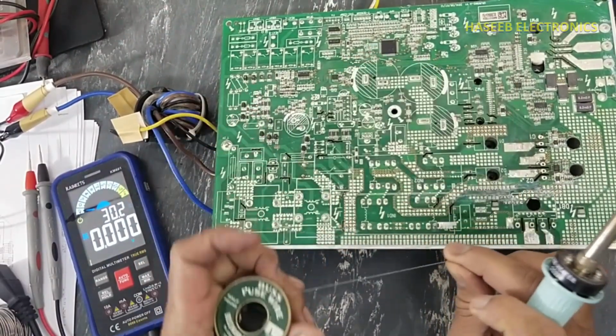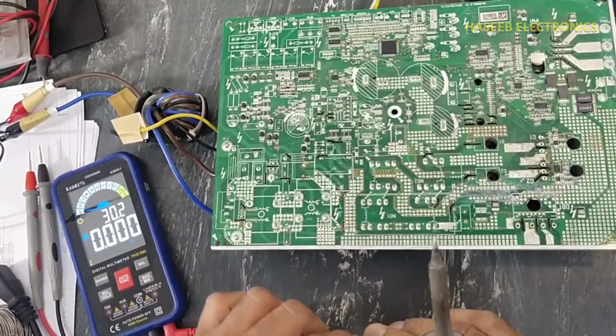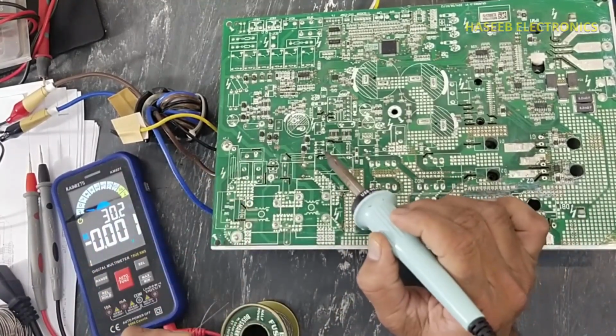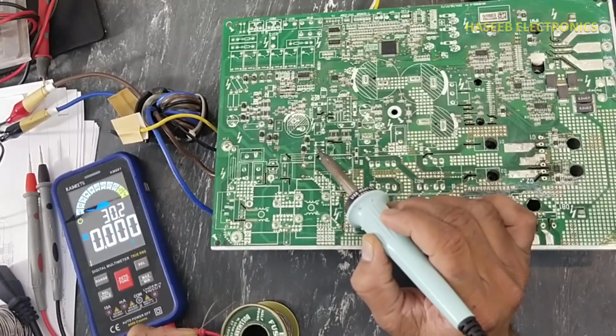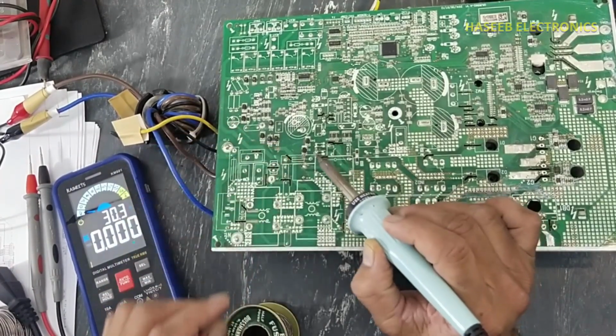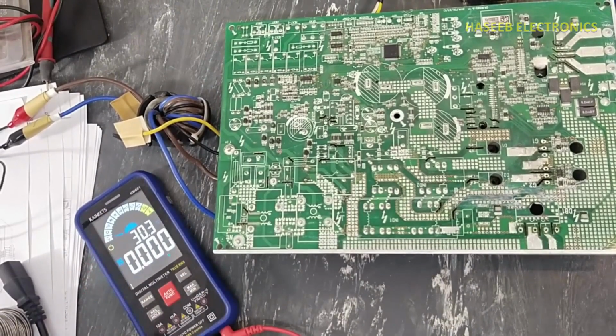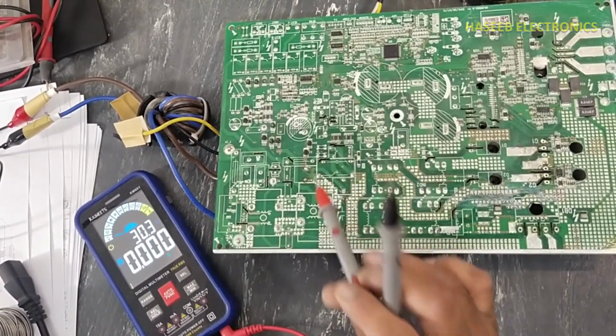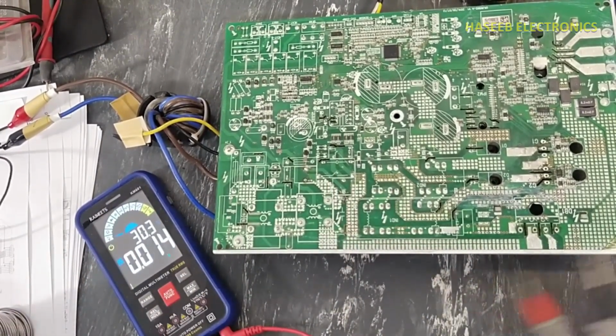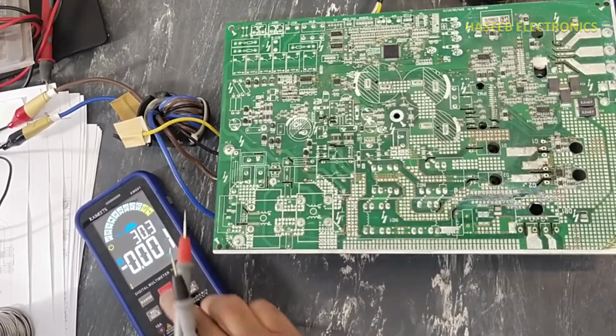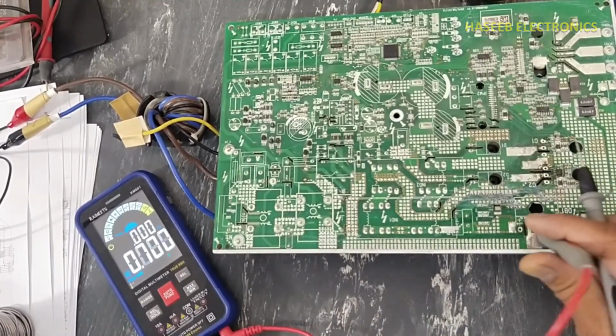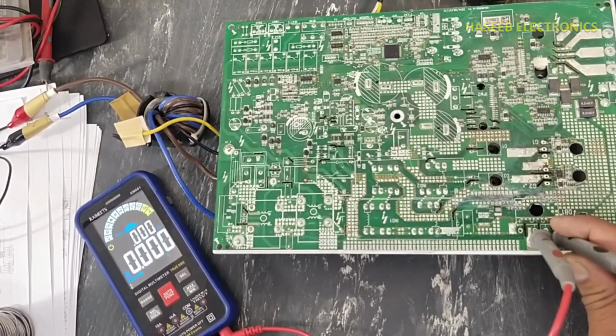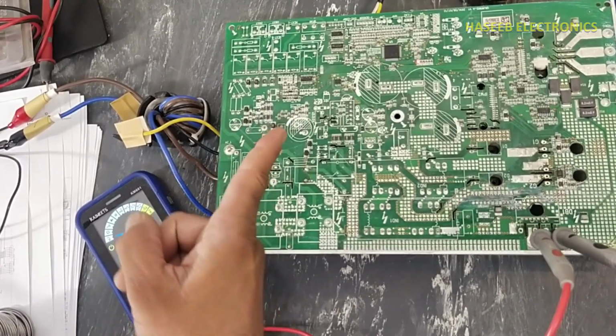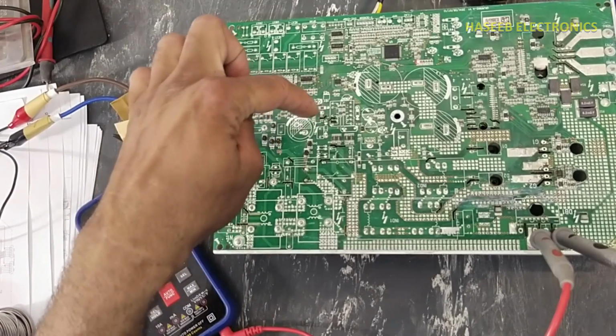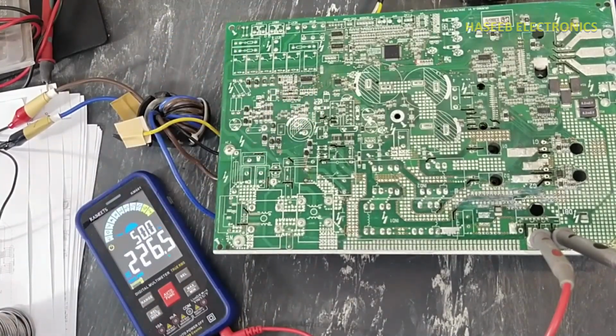I will connect a 1 ampere jumper at these 2 points. Now I installed the jumper and I will check AC voltage at this point. The relay is now turned on. This relay is now turned on.